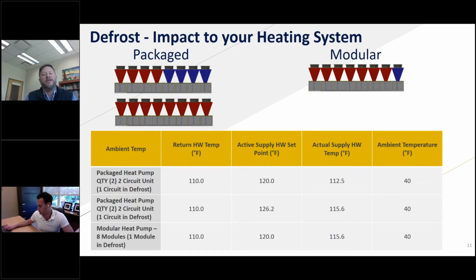a compressor off. If it's in a modular array, or if it's in multiple smaller package units, and let's say you have 2 compressors per module or 2 compressors per small package unit, if I have 8 modules, that's 16 compressors. I have a significant amount of capacity turned down across the entire system.